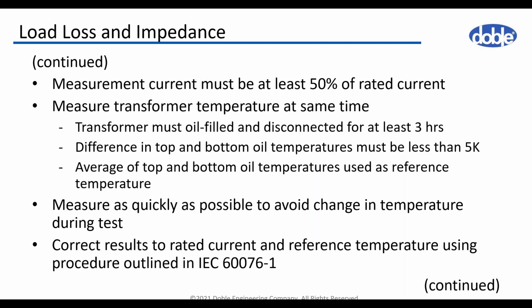The supplied current should be equal to the relevant rated current or at least 50% of the rated current. Load loss results are corrected to the reference temperature, and this is 75 degrees as per the procedure outlined in IEC 76 part 1. It is important to measure the transformer temperature during this test correctly. Otherwise, the result will contain significant error.